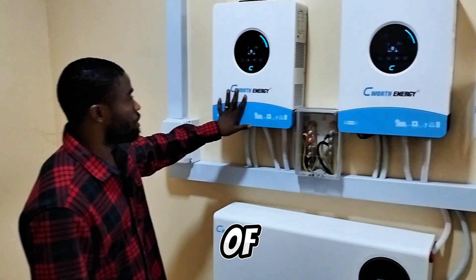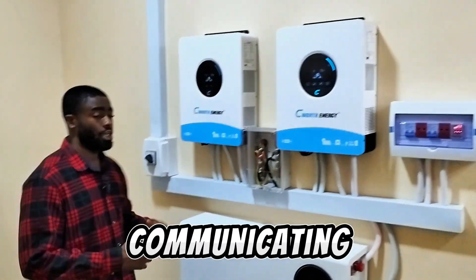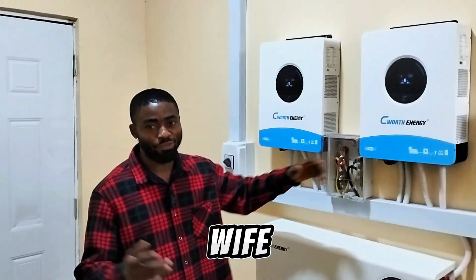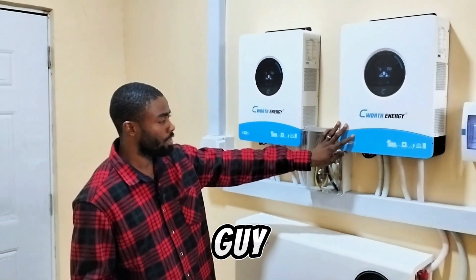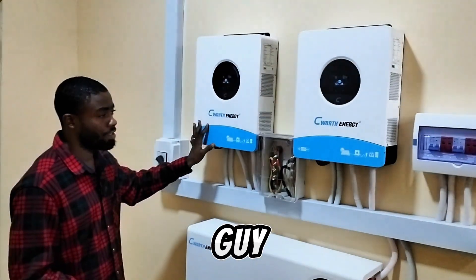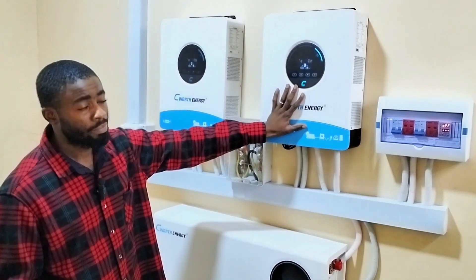Up here we have two units of 6kW inverters from C Worth Energy. These two inverters are communicating together — like a husband and wife. Here we have the master and the slave. The output of this inverter is connected to the output of the other, the input is connected to the input, and the neutral is looped to the neutral. This one serves as the master or primary, and this one is the secondary, which is the slave.